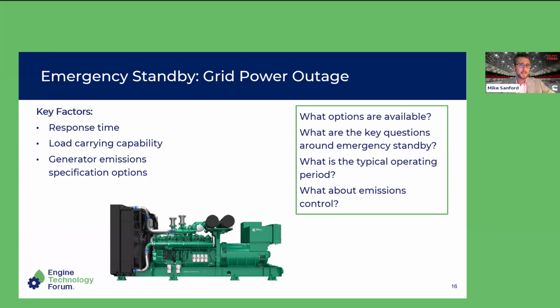In many cases, these generator sets and the engines within them are subject to permitting requirements — both at the federal level through the EPA, where the engine manufacturer is responsible for qualification and certification of the engine, and a locally derived or mandated permit, typically at the state or local process level. To satisfy those emissions requirements, it's not uncommon to see additional technologies deployed alongside the engine generator to reduce emissions output to levels determined by the local permitting authority or air board.